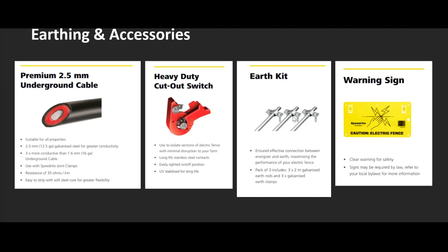Then you've got the earthing kits - 2 metre long, 10 to 12 mil diameter galvanised steel rods, hardened, so relatively easy to drive in. The narrow profile sometimes makes them easier to drive in, as long as you've got the right tool to hit them with. Depending on your ground type, you might favour those, or a wide profile steel post or some scaffolding tube. Whatever it is, having enough of it in the ground and making sure your connection to those earth rods is sufficient is really important.